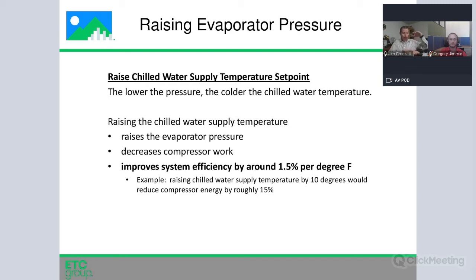So the first one is raising the evaporator pressure or raising the low side. If the inlet side of the compressor isn't at quite as low a pressure, you don't have to do as much work to get to the condenser pressure. And the most common way of affecting this is by increasing your chilled water supply temperature. If your building can get away with 50-degree water instead of 42-degree water, you can save quite a bit of energy. What you're doing when you raise the chilled water supply temperature is making the refrigerant cycle not have to run as cold. You raise the lower end of your pressure.